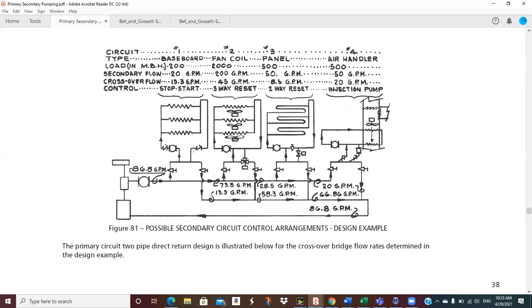And then of course, on your return side, I start out with a small pipe because I only got 13.3 GPM. Then I pick up the 45 and it steps up to 58.3. And I pick up the 8.5. And so it's up to here. And then we get the entire return back around there. Got our air separation compression tank over here, all that stuff going on.